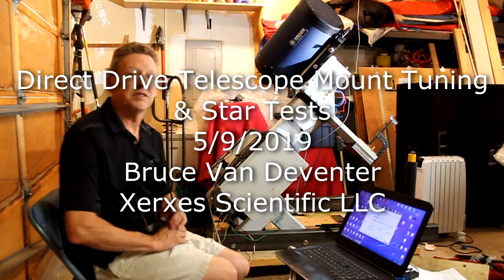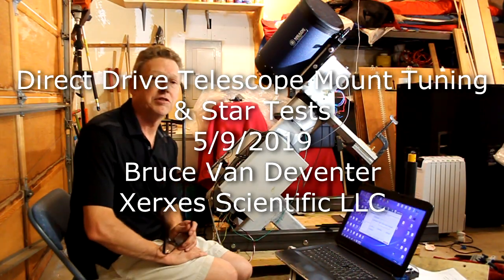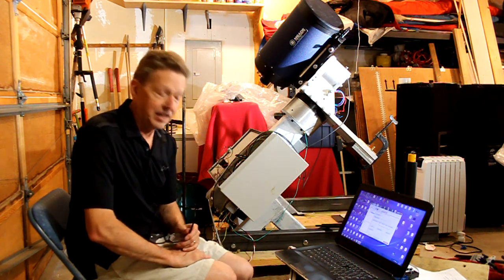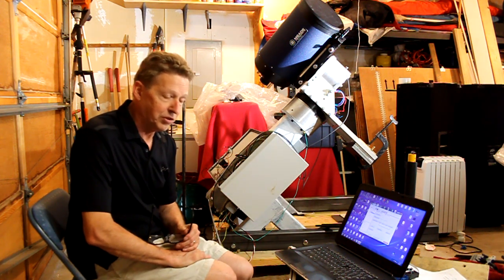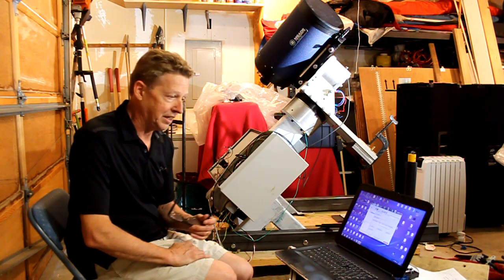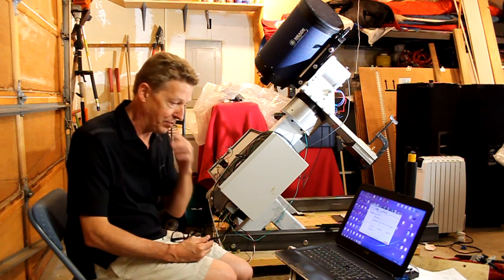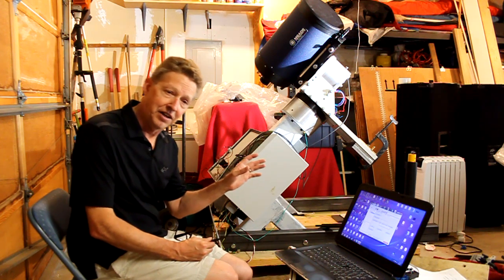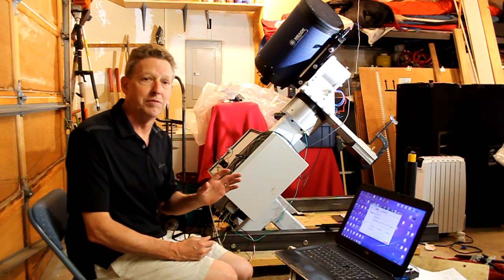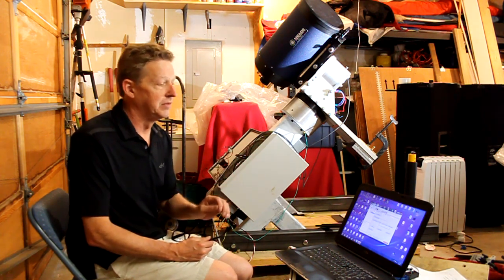Okay, so I want to talk a little bit about servo drive tuning. Every servo has some tuning required to get it to work optimally, and it's really critical in a direct drive mount, because there's no gearing to rely on. The stiffness of the mount is all coming from the motor and the control loop.